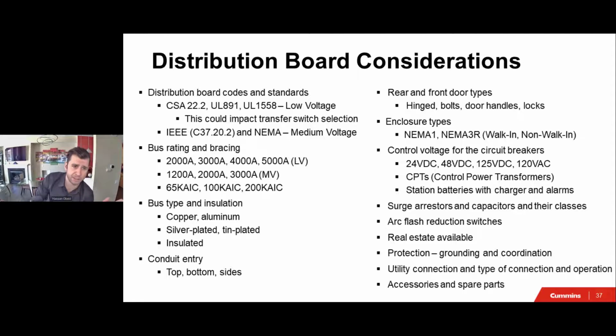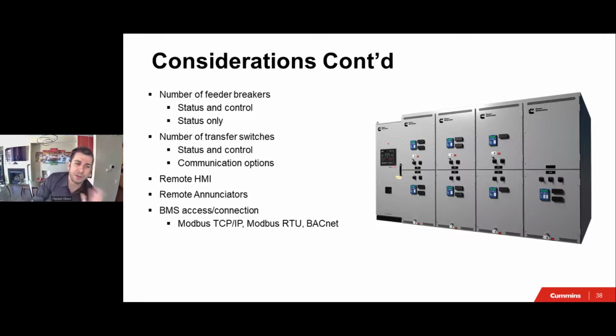Accessories, are there any accessories? And then the number of feeder breakers that we're controlling, is it and transfer switches? Are they control only or status and control? Is there a remote HMI in the system, remote annunciators, and what is the connection to a SCADA or BMS system? So print this out, use it as a checkpoint and ask, did I cover all those points when specifying switchgear or a switchboard? Just use it as a reference.